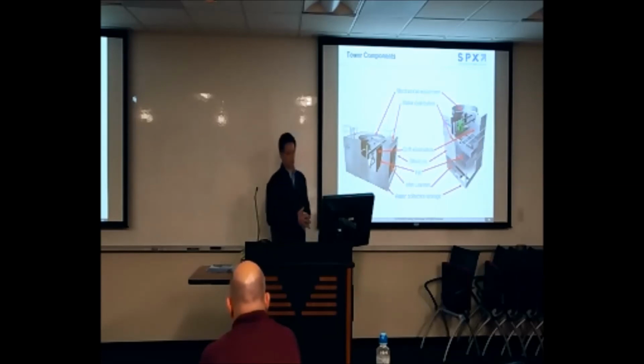To start the maintenance discussion, one thing that we like to recommend to everyone is that if you are out having eyes on the tower weekly or maybe bi-weekly, you are doing better than probably 80% of maintenance crews out there. The reason you want to be out there regularly, even if you're not going in and really looking at the gear reducer or checking the oil level, is it will give you a gauge of what your tower's doing. You'll be able to hear it. You'll be able to see, okay, this is what the tower sounds like. Go back the next week, it sounds a little different.